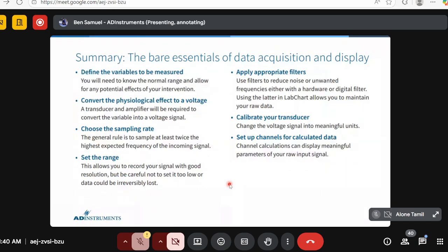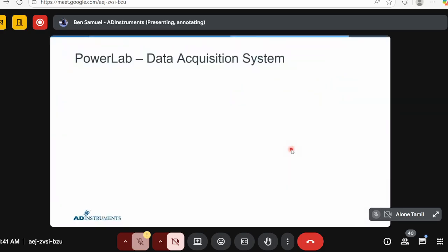In summary, about the basics: define the variables you need to measure, convert the physiological effect to voltage, that is nothing but sampling, choose the proper sampling rate, set the proper range, apply the appropriate filter, and then these two are additional points. If your transducer needs a calibration, you can do a calibration and set up the channels. There will be a lot of channels available. A few channels you can use for acquiring the data, and the rest of the channels you can use for multiple calculations, like the arithmetic and the cyclic measurements. You can use them for various other calculations. Any questions so far? Okay. If anything comes up, we can discuss it towards the end of the demonstration also.